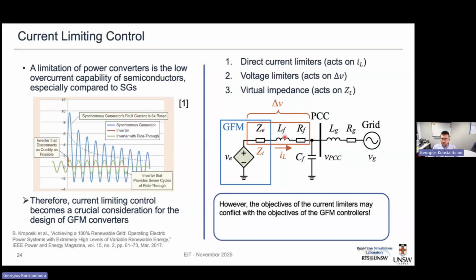All this sounds good, as in we can achieve these goals, but the biggest issue we have is that the moment we start trying to limit the fault current we get out of the converters, we have a fundamental conflict between the objectives of the grid forming control, which was this self-synchronization and the ability to maintain this internal phasor of the voltage, and our limiting of the current. So we need to better understand what is happening with these converters and how the current limiting methods in grid forming converters affect the converters themselves and the system as a whole.